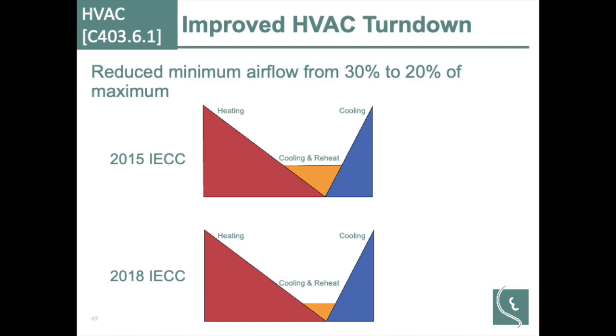Now there may be some physical limitations in there, and so that would be something to discuss with code officials, because I realize that there is a minimum fan speed way back here at the air handler. Now if all of your zones have turned down to that, then you may begin to look and say, well, do I even need to operate the system at all? Or can I turn the fan off because no zone actually needs it? So there may be some additional programming that may be beneficial in here. So, yes.